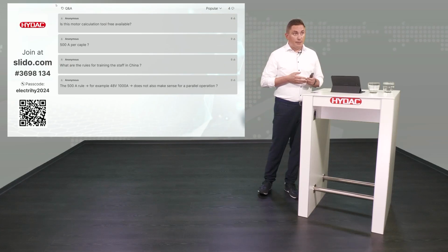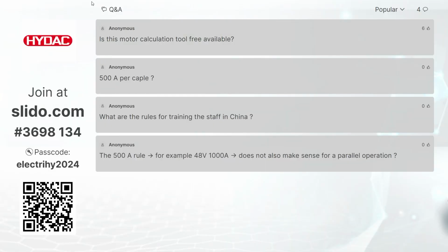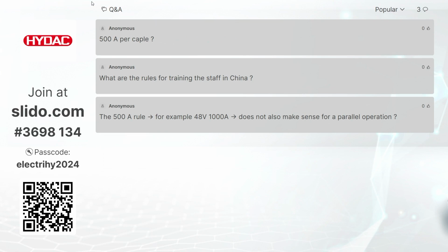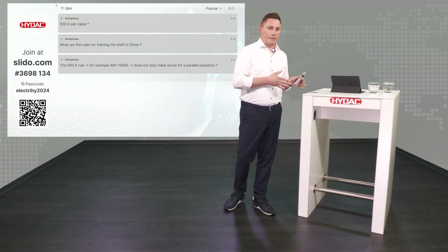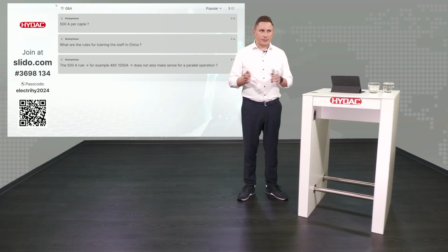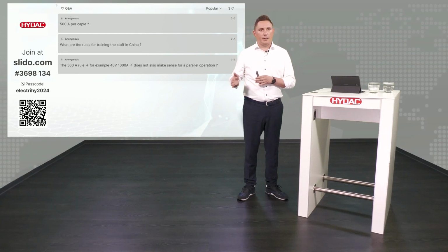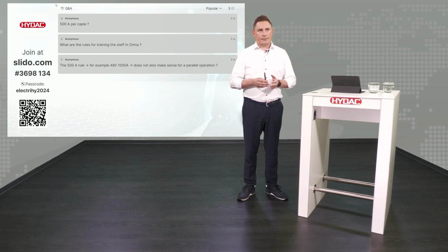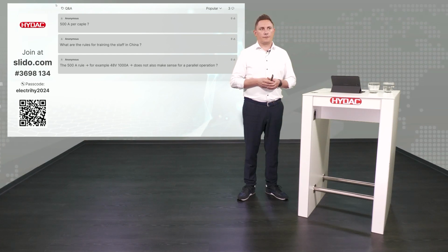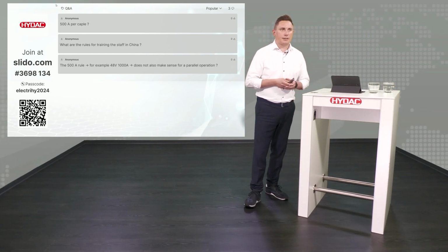The second question is closely connected to the third, the 500 amps rule. For example, with 48 volt 1000 amps, does it not also make sense for a parallel operation? That means you have several components in parallel, or several cables, or even several inverters, that each can carry 500 amps, but in the end you'll have a system current that is more than 500 amps.